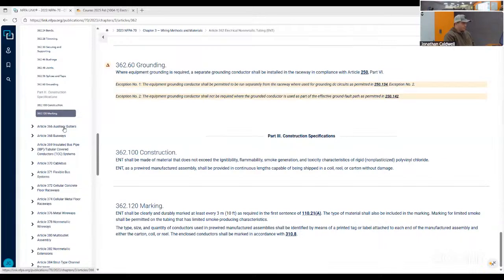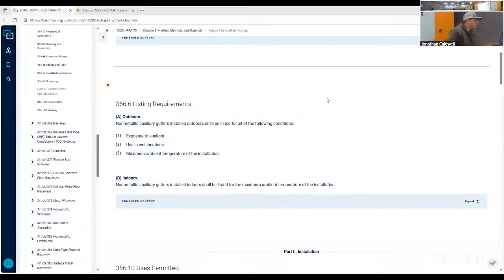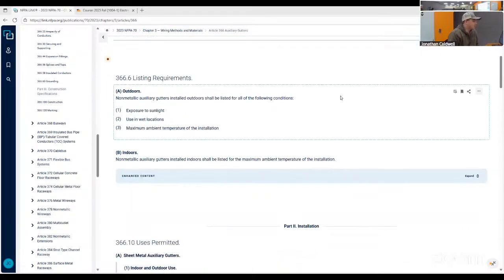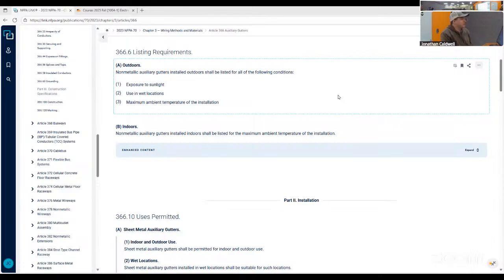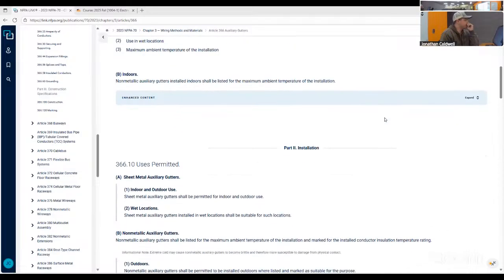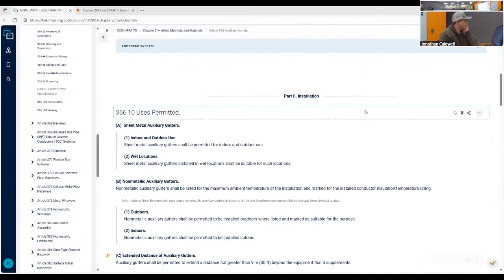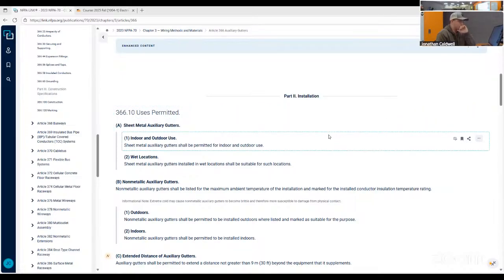Auxiliary gutters. Yeah, let's cover them. They're not in class, but everyone uses gutters, right? So, listing requirements, outdoors: non-metallic auxiliary gutters installed outdoors shall be listed for the following conditions: exposure to sunlight, use in wet locations, and the maximum ambient temperature of the installation. Non-metallic auxiliary gutters installed indoors shall be listed for the maximum ambient temperature of the installation. Uses permitted, sheet metal gutters: sheet metal gutters shall be permitted for indoor and outdoor use. And sheet metal gutters installed in wet locations shall be suitable for such locations.